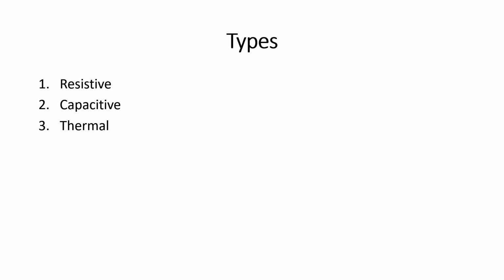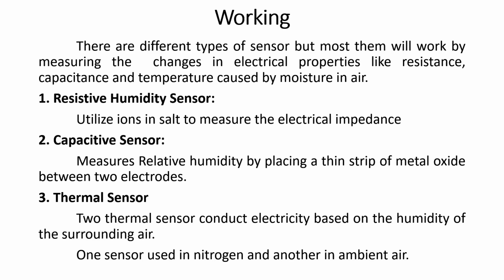Types. It has three types: resistive, capacitive and thermal. Working. There are different types of sensors, but most of them work by measuring changes in electrical properties like resistance, capacitance and temperature caused by moisture in the air. The first one is the resistive humidity sensor. It utilizes ions in salt to measure the electrical impedance. The second one, the capacitive sensor, measures relative humidity by placing a thin strip of metal oxide between two electrodes. Thermal sensor. Two thermal sensors conduct electricity based on the humidity of the surrounding air. One sensor is used in nitrogen and another in the ambient air.